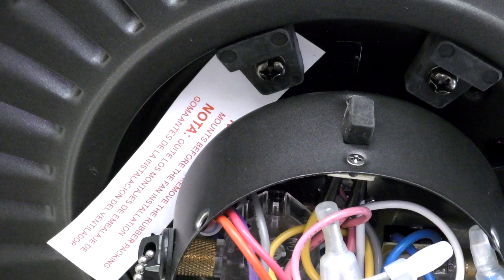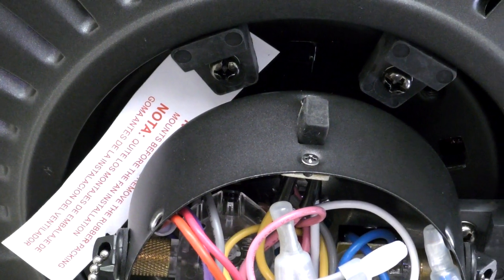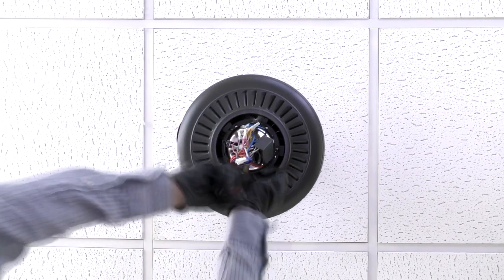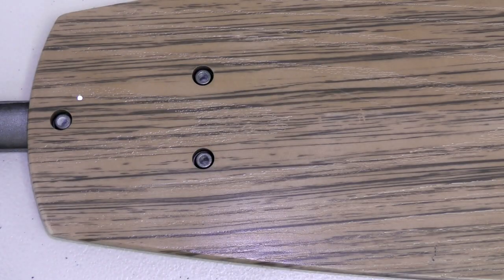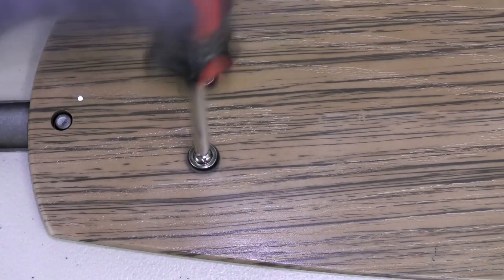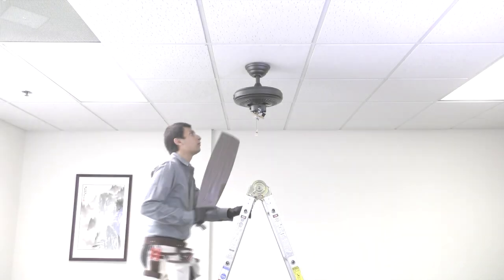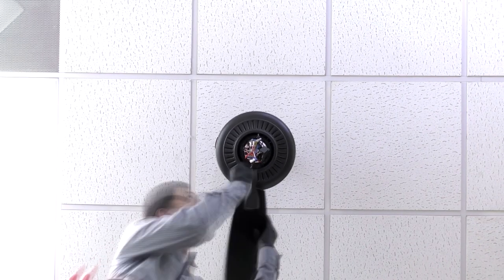The fan motor assembly is shipped with rubber packing mounts to prevent movement during transportation. Use a screwdriver to remove all five packing mounts from underneath the motor assembly. Attach the blade to the blade arm by aligning the holes and inserting the blade screws securely. Repeat the process for the remaining blades. Install all three fan blade assemblies by aligning and tightening the pre-assembled blade arm screws onto the motor.